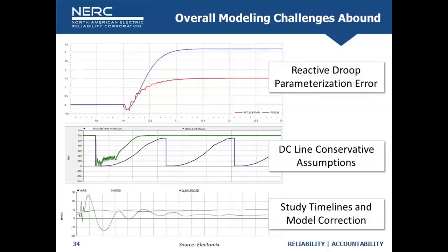The middle plot shows a good example of studies around a DC line, and whether or not that HVDC circuit can maintain stability. The positive sequence RMS simulation showed that the unit goes unstable. That defined an operating limit. But when they ran the EMT studies, they actually saw that it's stable. At that current operating mode, the unit's able to respond and have stable operation. But what the transmission entity did was say, we're still going to rely on those positive sequence simulations to set the operating limit because we see instability there. So it's essentially a form of margin: we know it's stable, but it's marginally stable and the tools are starting to fall apart, so we need to have some buffer in there. That's been a recommended practice across the industry, to build in some amount of margin to ensure stability, and they're using it in that way.